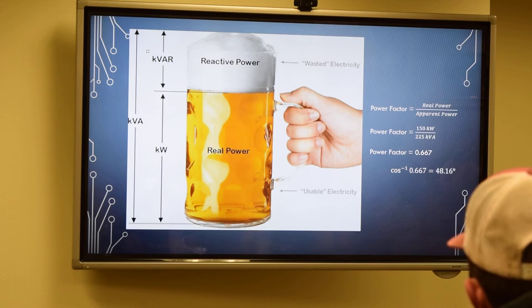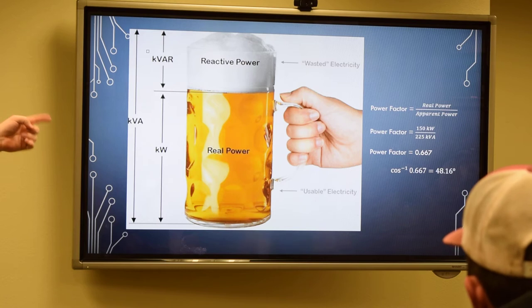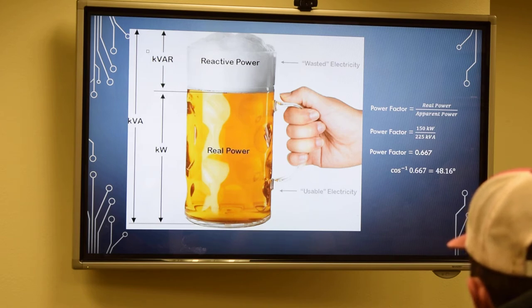So an example right here, the 150 kW divided by, say, a 225 kVA transformer. Your power factor is 0.66, and we'll denote that as 0.66 lagging. When we take the cosine inverse of that power factor, that 48 degrees, we use that more in the relay side of it. That's how we calculate the phase angle between your voltage and your current. And so that angle is important to us when we start programming relays.